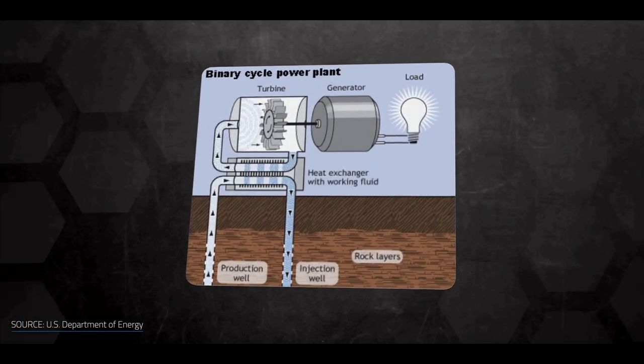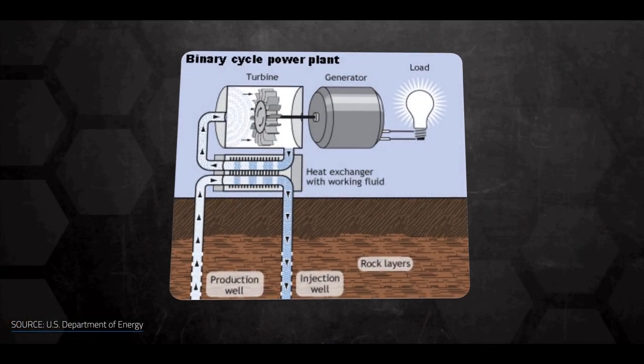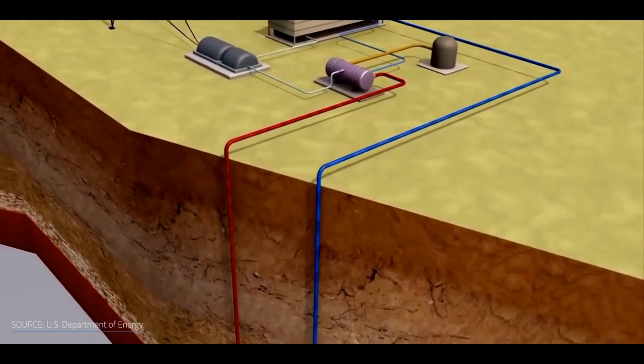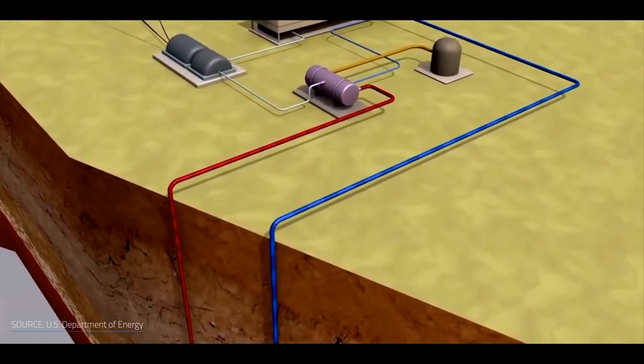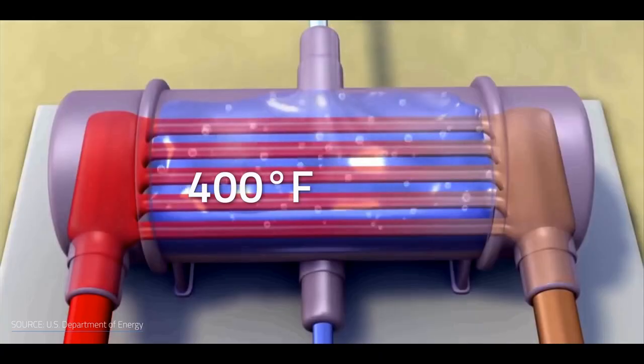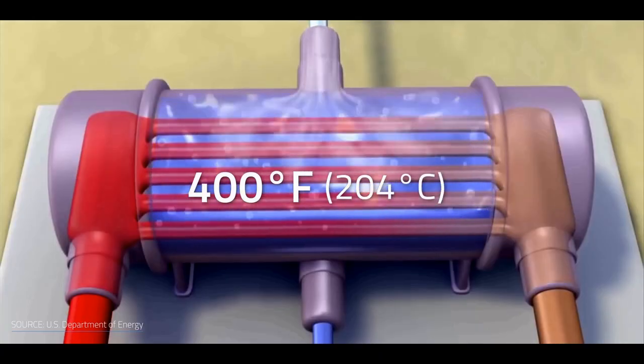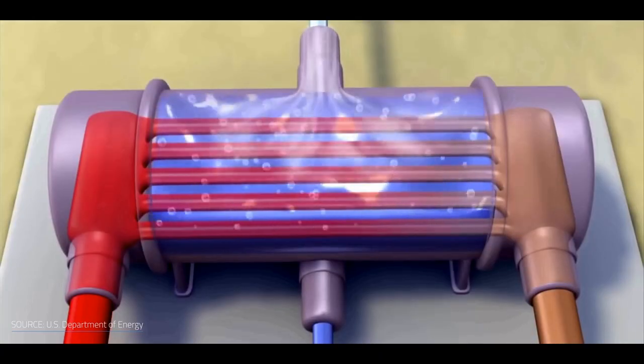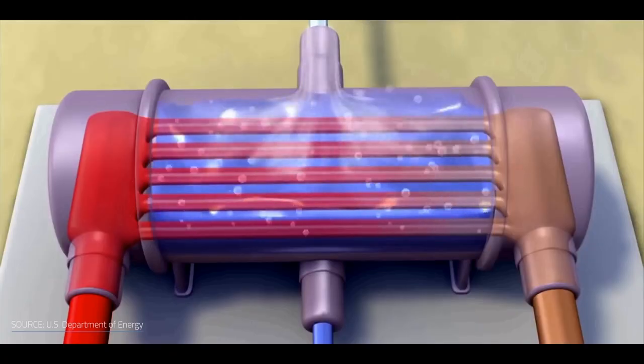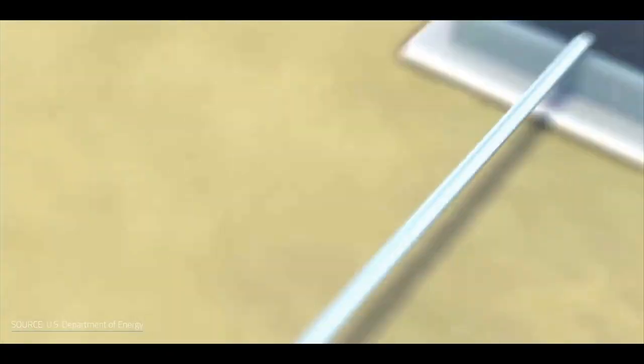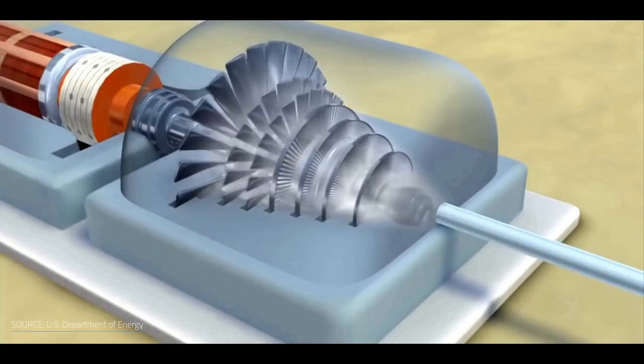Of all the options, binary cycle power plants are the newest and most sustainable. Unlike other designs, binary plants don't use the underground hot water to generate steam directly. After extracting it and further heating it to about 400 degrees Fahrenheit (204 degrees Celsius), they run it through a heat exchanger, where the geothermal water transfers its heat to a secondary liquid with a much lower boiling point. This generates the steam that spins the turbine.